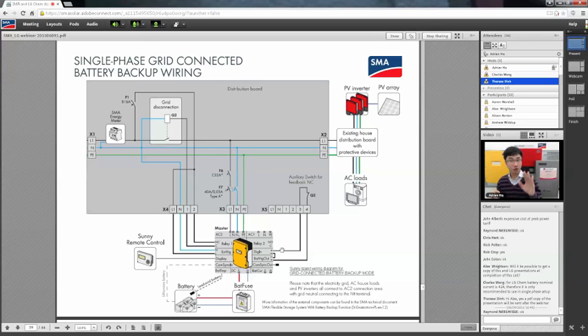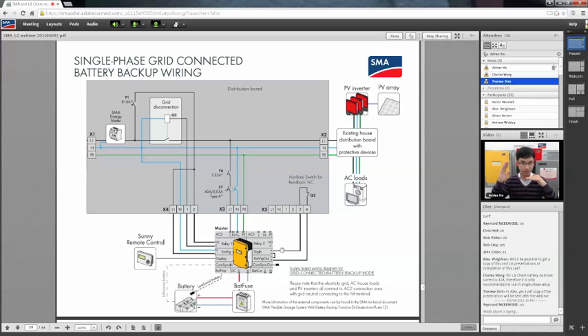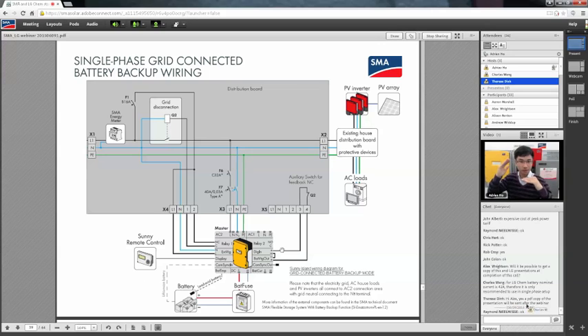Now the grid restores, say around peak time, 7pm, prime time. Grid restores, but Q2 would not close immediately—it won't close right away, but the Sunny Island knows the grid is already there. This all takes place at the Q2 contactor. 60 seconds later, the island will close that Q2, bringing the whole system back onto the electricity grid. If there's still sun and things are fine, at this reconnection the whole thing is seamless. So, only at the disconnection is there a 5 second blackout.